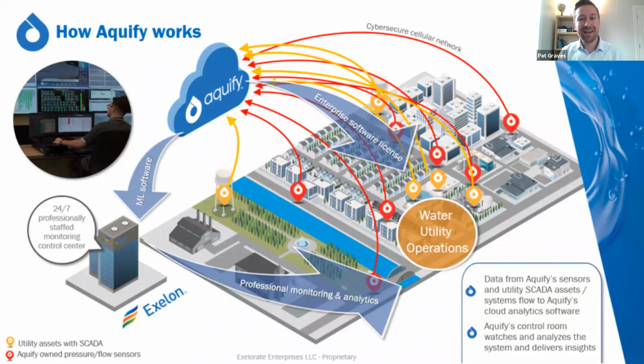It's okay, George, if we leave it on this slide. The purpose of the previous slide was just to say it's more than—we were pleasantly surprised to find much more than water loss and leak detection as benefits of the Takadu and Aquify solution. By having all these monitoring points out into the distribution network and using machine learning and advanced analytics, we're able to find all types of things: PRVs failing, pressure issues that might cause pipes to burst in people's homes or low water pressure, or slow flow speeds that could cause water age to increase beyond what's allowable to maintain disinfectant residual levels. When you have the data, we find so much value.